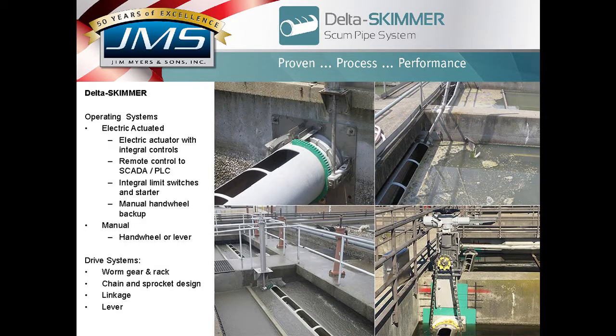You're looking at several applications we've got out there in the field. You've got electric actuated systems with electric actuators. Typically, we recommend, and we're married at the hip on an OEM basis with Rotork, the Rotork MX and Rotork IQ actuators. But we can provide any type of actuator that a particular plant might need. We can certainly handle that. Of course, the actuators include integral limit switches, controls, and motor starters, and we can include Modbus, Profibus, fieldbus, whatever is needed to communicate with the SCADA system at a particular plant. The electric actuators have a manual hand wheel backup too, in all cases.